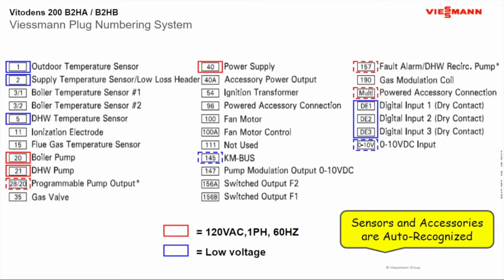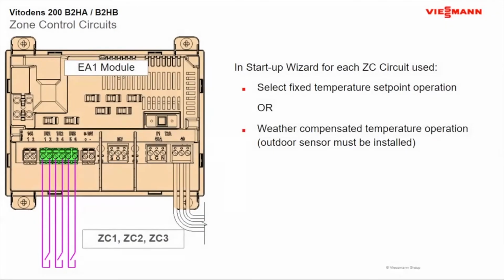So a lot of times I used to tell guys to hook the outdoor sensor, put it on a small piece of wire and throw it in the cabinet or somewhere, and then make sure you adjust your outdoor temperature settings so it doesn't come on. Your Z1, your Z2, your Z3. So these could be end switches. These could be thermostats coming right to the boiler. Remember, they have to be contact free, voltage free, sorry, with no voltage on either an end switch or thermostat.